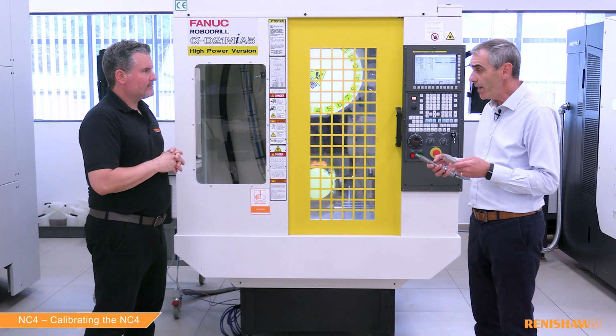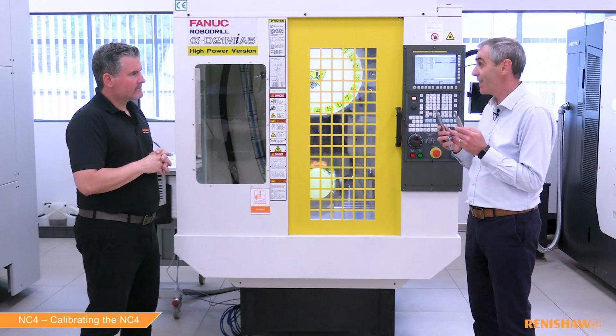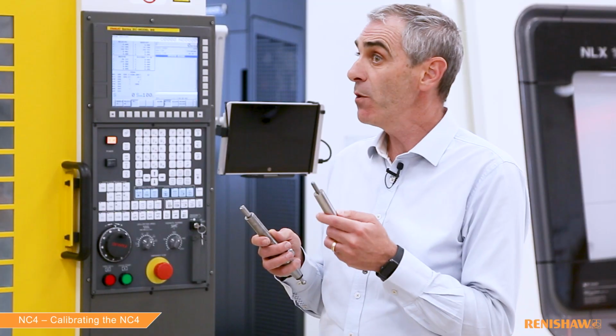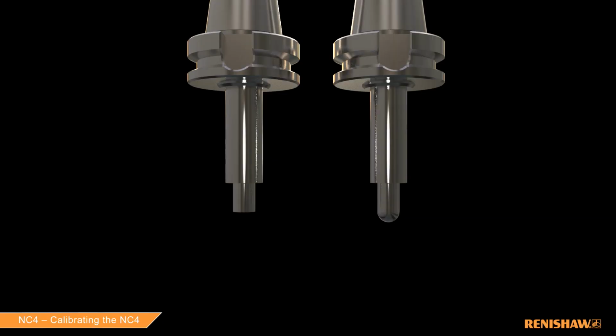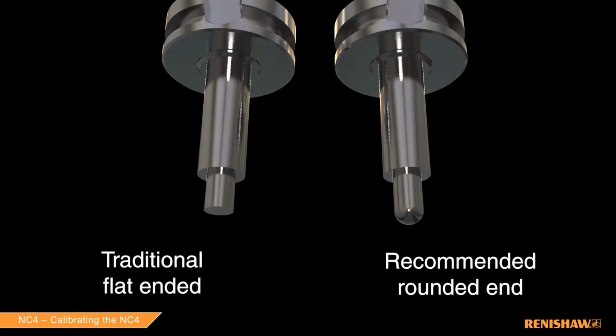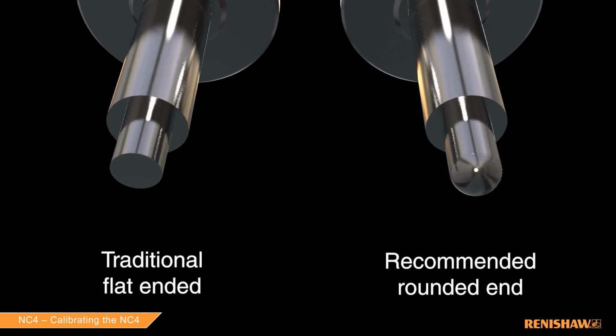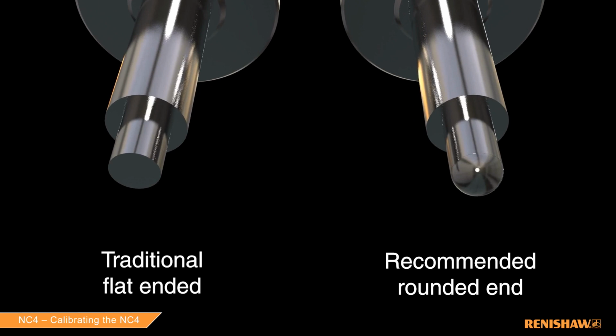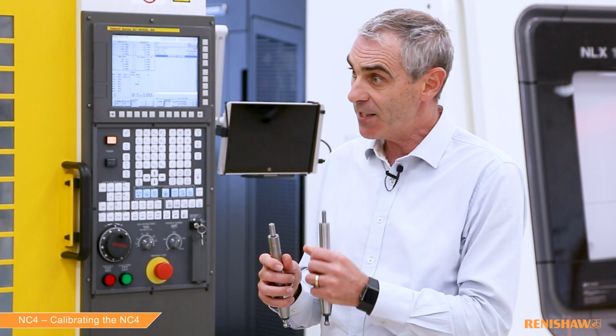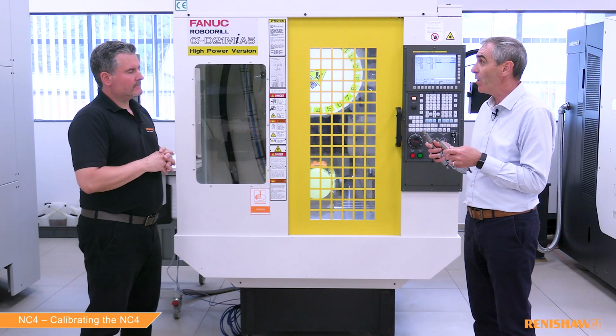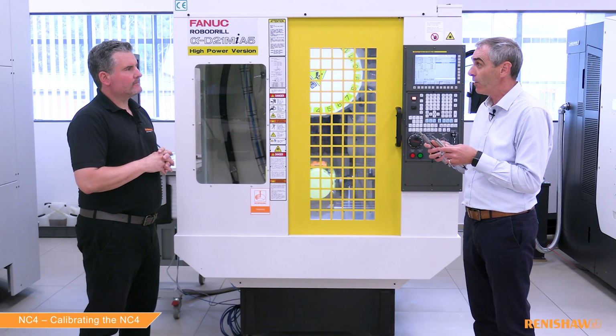So for the alignment, we use a specialist tool. Do we use the same type of tool for calibration? Yes, we use exactly the same tool, the same calibration tool. And as I mentioned before, there are two types. We've got the traditional method, which is flat bottomed, and we've got a new type, which is a radius. We always recommend the radius value with the NC4 because it has a less reflective surface on the end, which helps when setting up the beam very, very accurately.